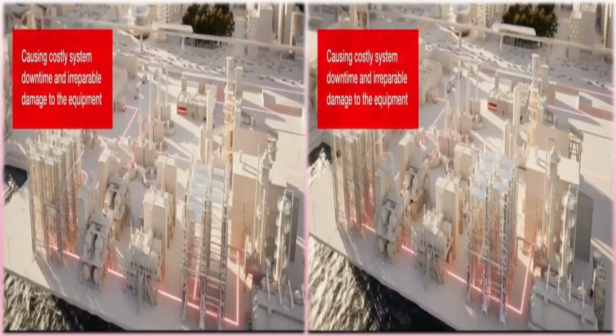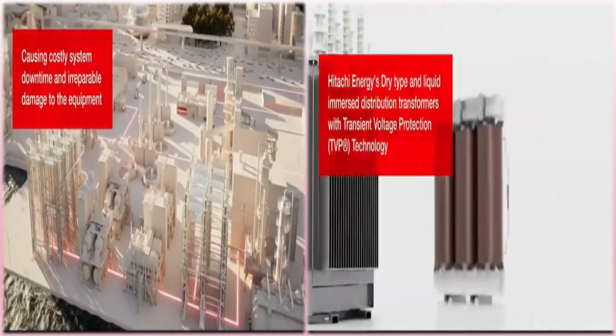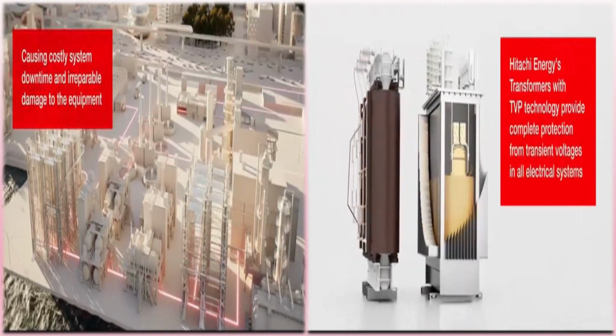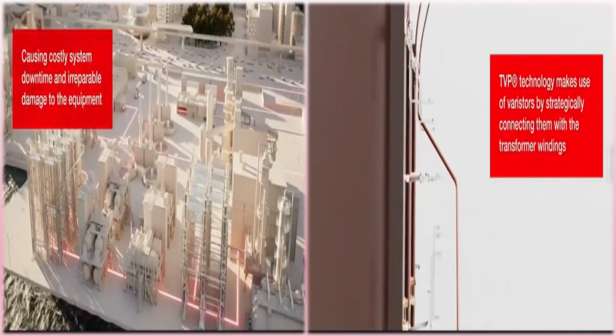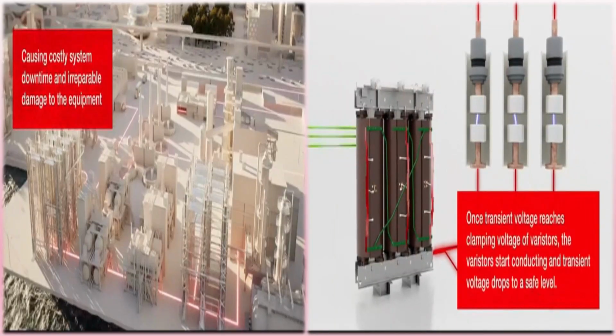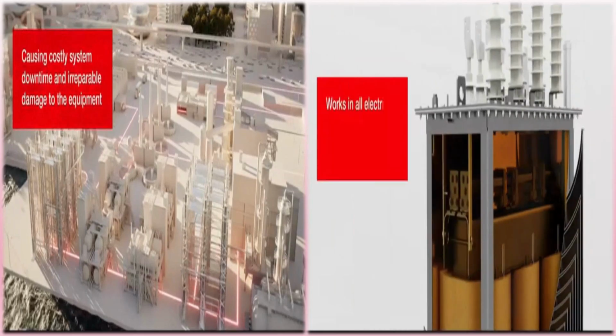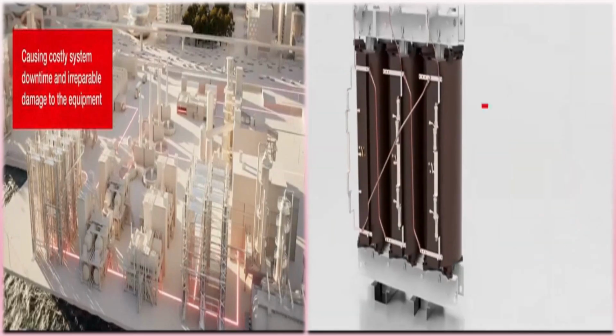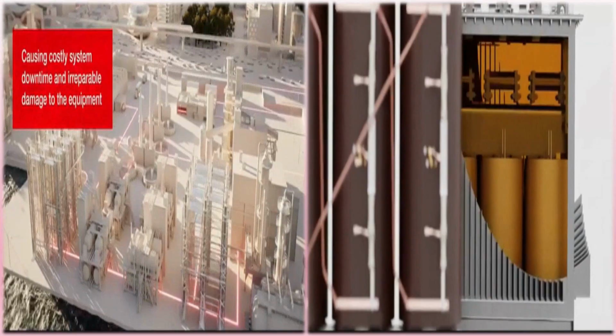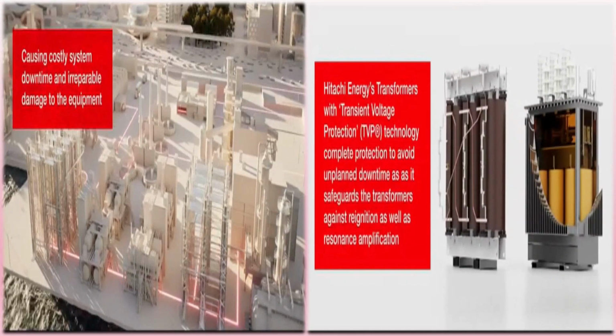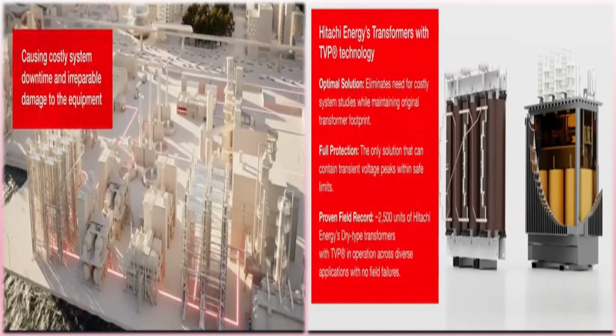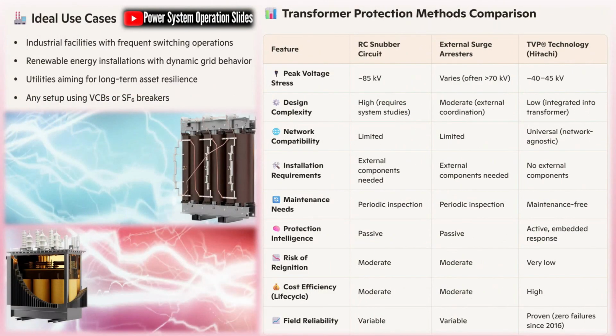the system. These transients typically have high frequency, up to several megahertz, short duration, microseconds, and high peak voltage, often exceeding 60 to 80 kV. TVP varistors are strategically placed within the transformer windings to intercept these transients. As the voltage rises beyond a safe threshold, the varistors conduct and clamp the voltage, reducing the peak stress to around 40 to 45 kV, which is well within the insulation limits of modern transformers.